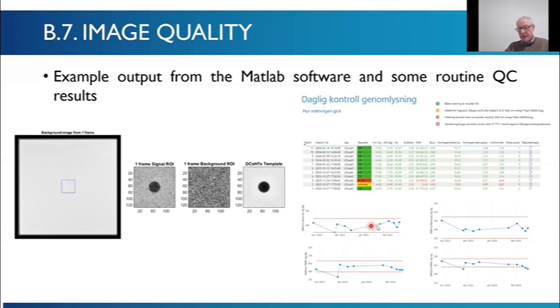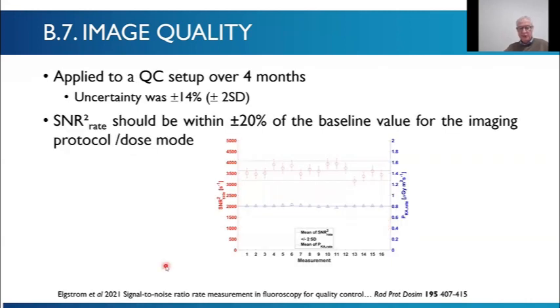Then you can measure the signal to noise ratio rate over time and see how it varies with dose rate. And Michael has done some work on this, published in Radiation Protection Dosimetry, where you can read more about it. You can measure within about 6% and about 14% to 2 standard deviations for a well-defined QC setup. So it's a very reproducible method.